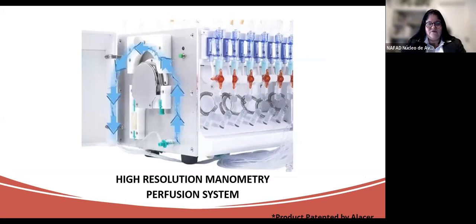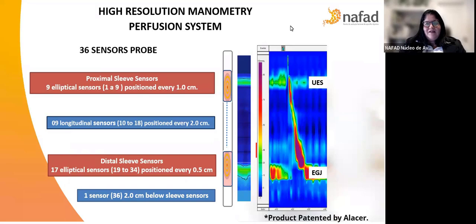Another advance is the continuous infusion tank, which allows the infusion of distilled water at a continuous and stable pressure. The infusion pressure is easily adjustable through the software. This mechanism does not require the use of old air pressurization tank.